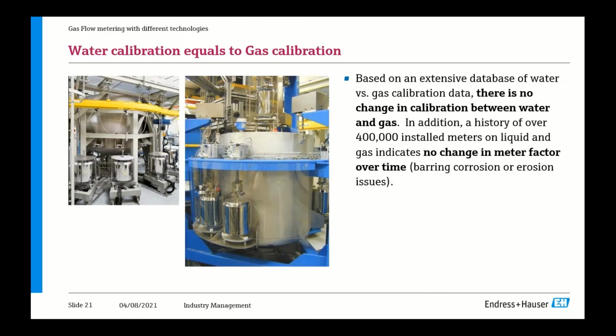First of all, thank you for the outstanding introduction of these technologies. Of course, we saw how different technologies could be selected for a specific application in natural gas, and we saw advantages and limitations as well. And thank you, Oliver, for introducing the Coriolis meter and telling how accurate and how stable a Coriolis meter is for gas measurement. But what about when the instrument is already installed outside and you really need to prove the stability of this meter, or even to know if it is still within specifications? Well, here is where the Coriolis technology takes the lead. Since proving any gas meter in situ is very difficult and complex, the stability of the Coriolis meter makes it ideal for use with gas.